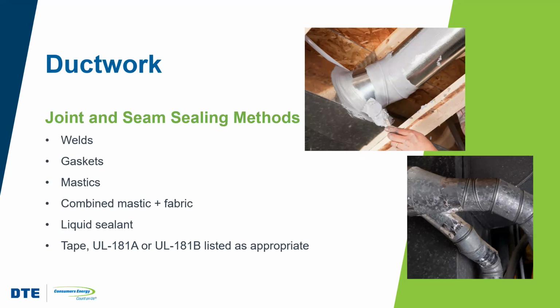Now, it doesn't do that directly. It doesn't say that you can't use duct tape. What it does say is that any tape that's used has to be UL listed. UL 181A for fiberglass duct and UL 181B for flex duct. And since duct tape doesn't bear those UL labels, it can't be used for sealing ducts.